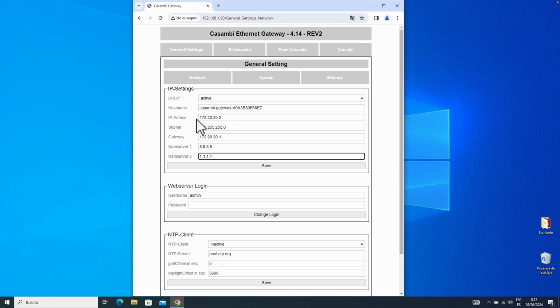It will take the IP that we have indicated, but if there is DHCP in the network, it will not take this configuration, and it will take the one that comes from DHCP. In the case of an Adquio Pro or Lite, in those 3 LAN ports that it has integrated, there is DHCP, so it would give you an IP, and it wouldn't have to be this one, so we're going to disable it. Very important. Then we click Save and Reboot.